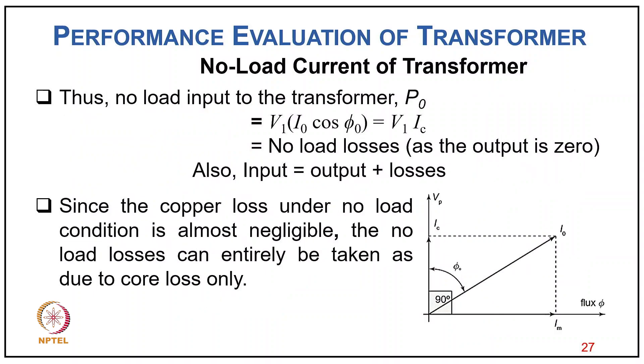The no-load input to the transformer is P₀ = V1 × I₀ × cosφ₀ = V1 × Ic. Since the copper loss under no-load condition is almost negligible (no-load current is around 1–2% of full load), no-load losses can be entirely taken as core loss only.